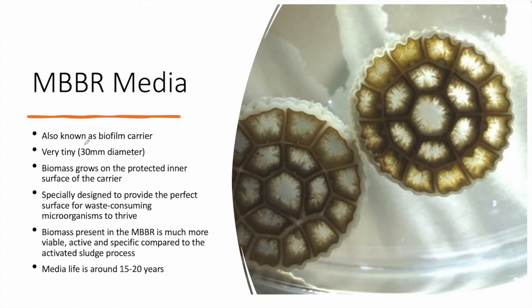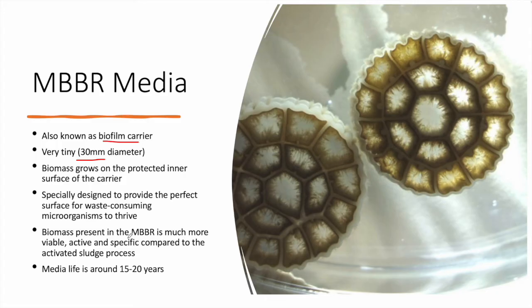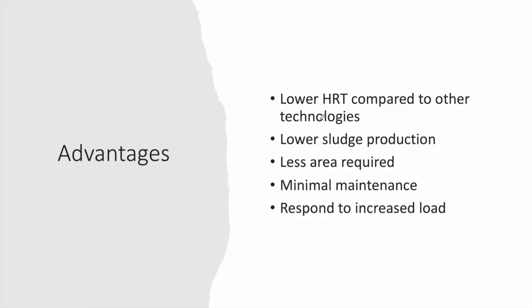Let's have a closer look at the MBBR media, also known as biofilm carriers. Zooming in, you can see the biofilms proliferating in the tiny pores. The diameter is usually 30 millimeters. The biomass grows on the protected inner surface of the carrier, which is specifically designed to provide the perfect surface for waste-consuming microorganisms to thrive. The biomass in the MBBR is of very high quality compared to activated sludge, with a very high removal rate for BOD, COD, and nitrogen. Media life can be around 15 to 20 years.